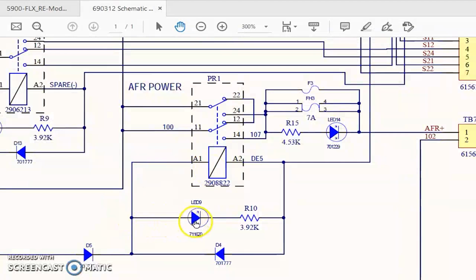It also enters into a light emitting diode through a 3.92K ohm resistor and makes it back to the DE5 wire. And then finally, there's a flyback diode only allowing excess voltage from an inductive load that occurs, or self-inductance, when the magnetic field in this coil for the relay collapses, to where if there's a voltage surge on the ground line, it can be dissipated back into the system and loop around in this path and slowly diffuse. So if DE5, now this DE5 wire comes from the A2 terminal, again, it's tied to all these things you see here, and it goes back into digital output 5 on either the DE3000 board or the DE4000 board, as I showed in that previous example.